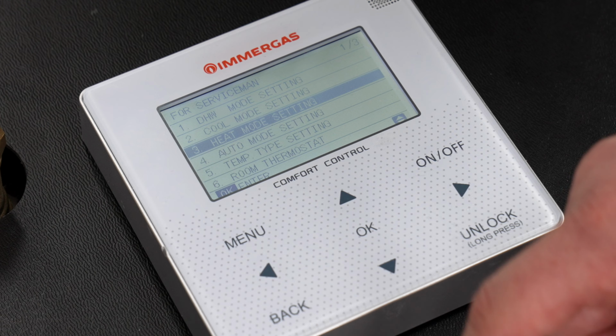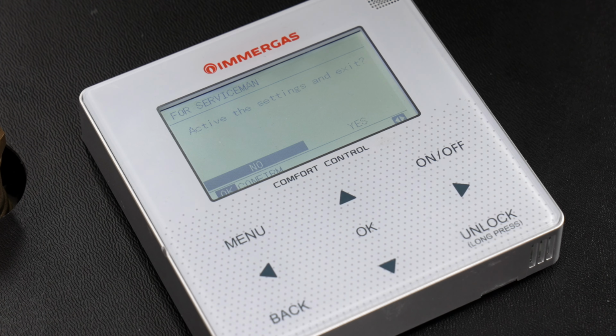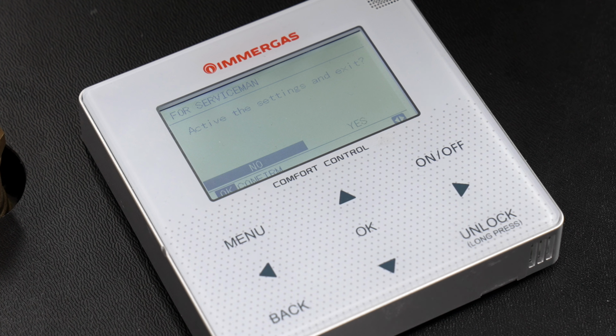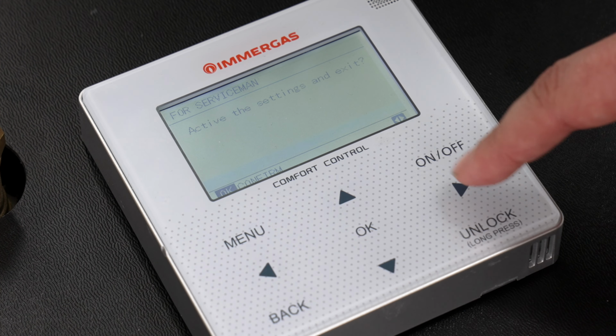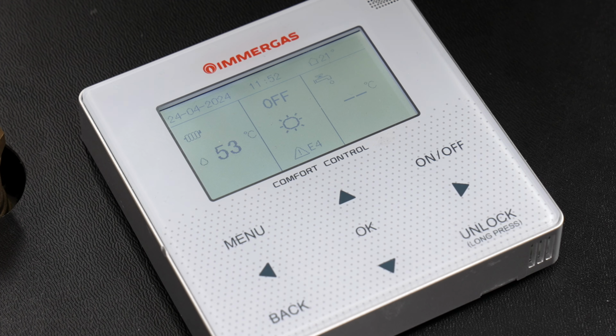You press back again. Any changes you make on the controller, you will always get this pop-up message. You want to accept this message, so activate the settings and exit. Yes, this will now confirm that you've saved all the changes. Move across to yes, press OK, and it takes you straight out to your screen.